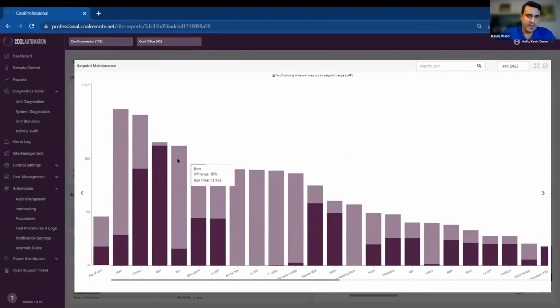But 85% out of range, there's probably some type of issue going on, whether it's an unrealistic set point that needs to be monitored a little bit more tightly, or the system is not properly sized, it physically can't achieve set point, or maybe there's external factors like a window or door being open, or something that needs to be maintained or fixed with this fan coil.